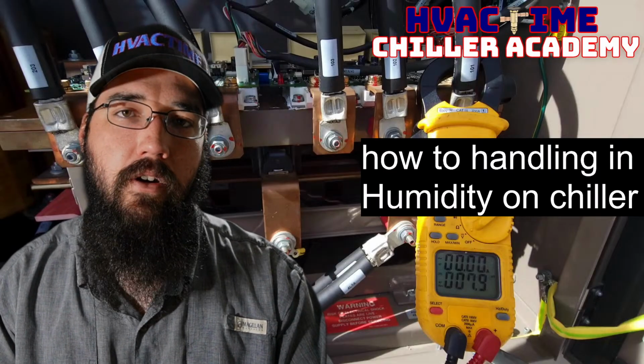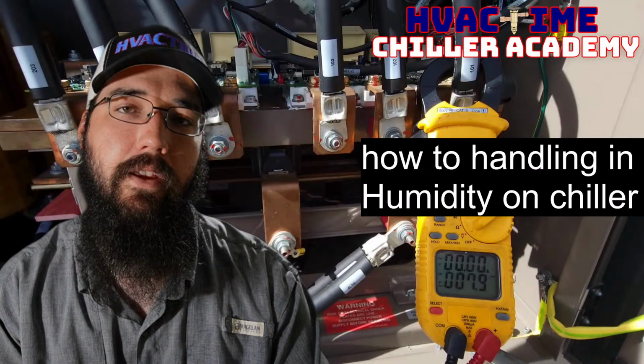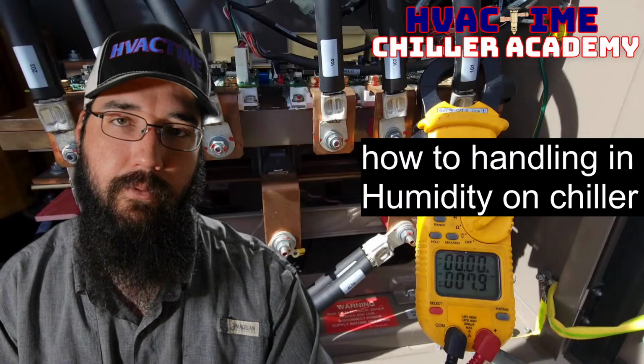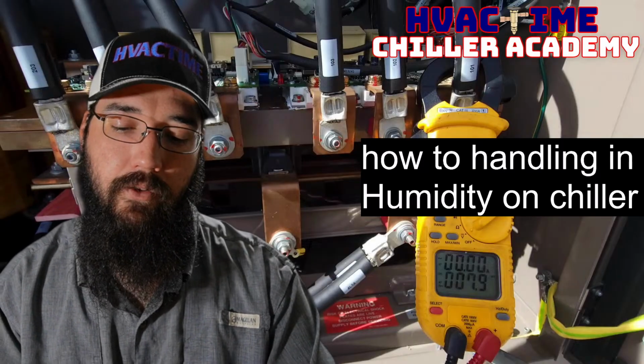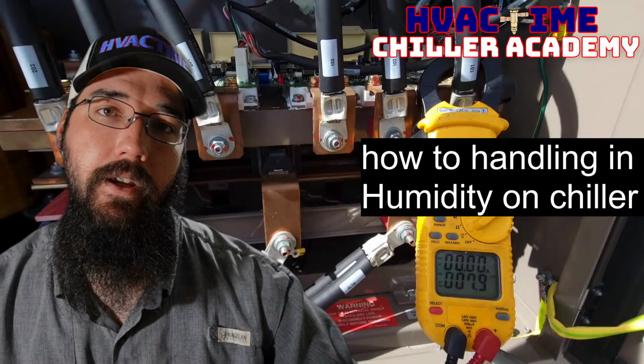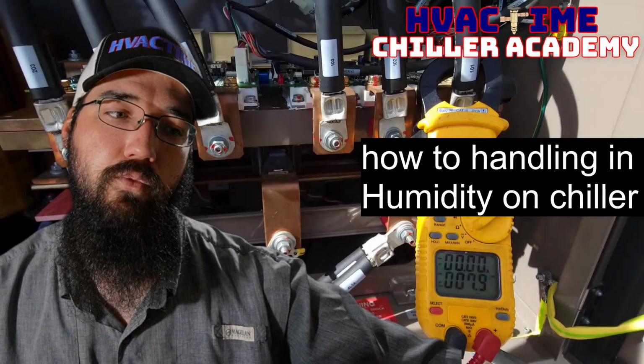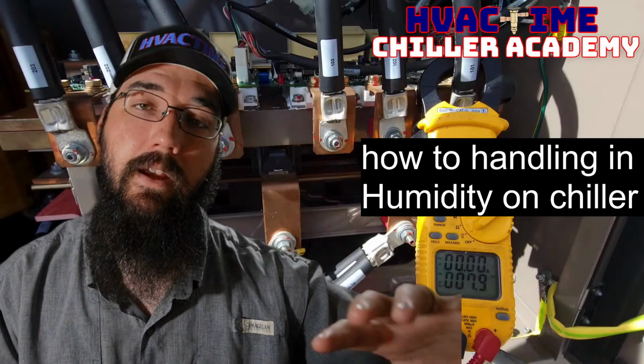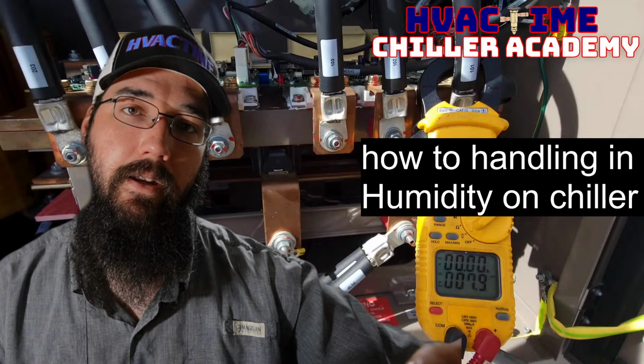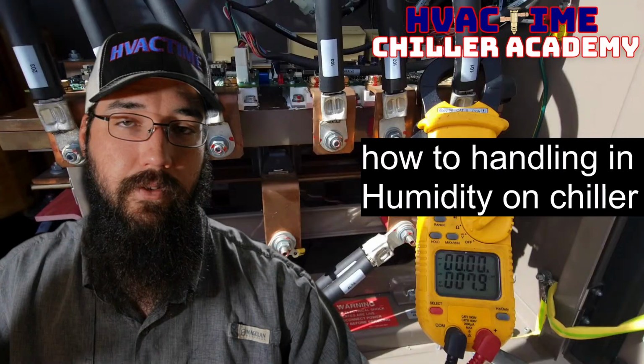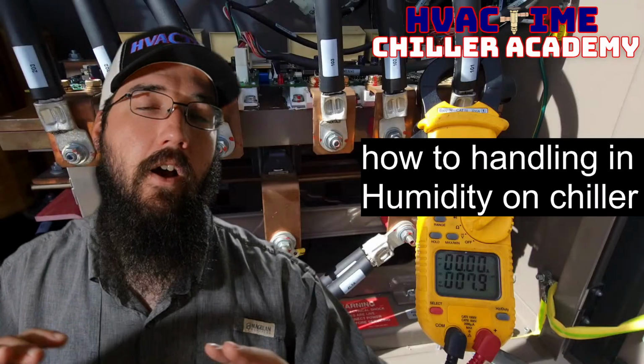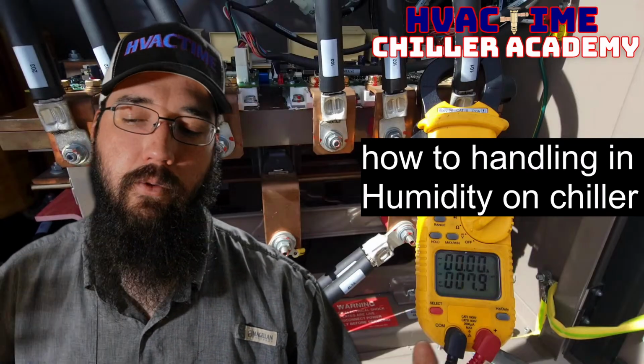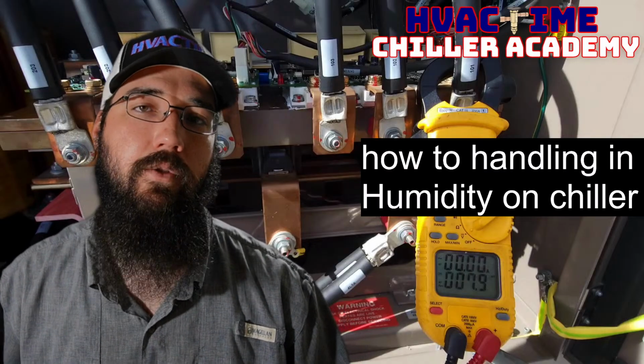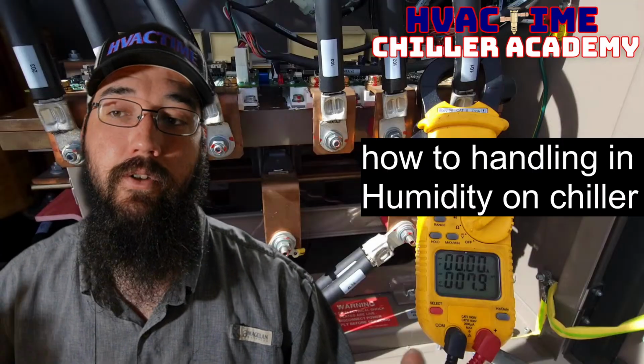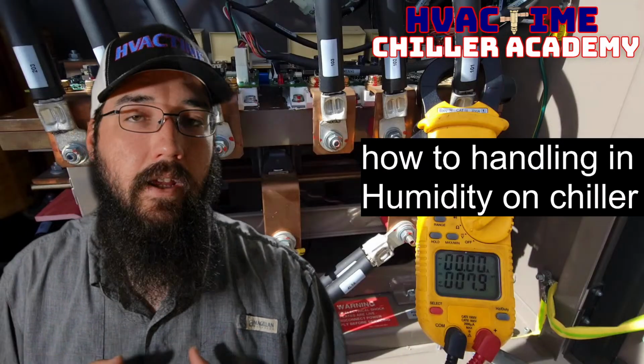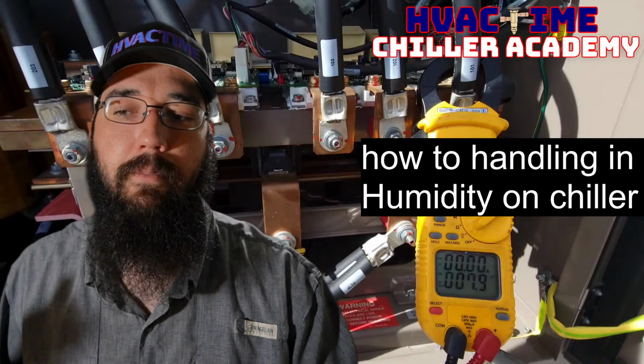So if our airflow on the space is correct, and we're actually flowing air, making static pressure, and we have the CFM through the coil that we need, and we've already gone to the extent of, say, lowering CFM a little bit to allow more dehumidification in the space, because that's part of it. If we can slow the air down on the coil, we can achieve better dehumidification. It's the exact same principles. Even though it's water in the coil, all the other principles are still the same. That 45 degree water is no different than trying to achieve a 45 degree saturation temperature if it was a DX coil with refrigerant inside. All of those principles still line up and match up step for step.